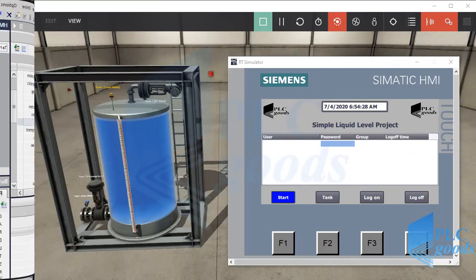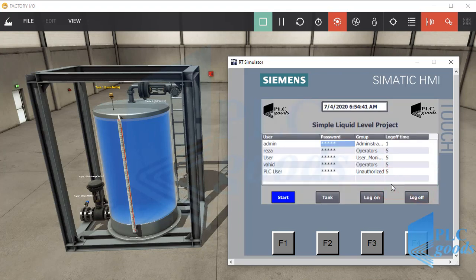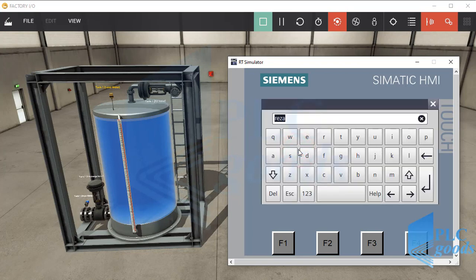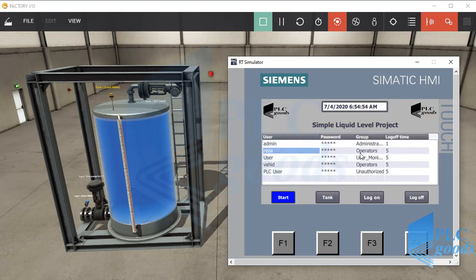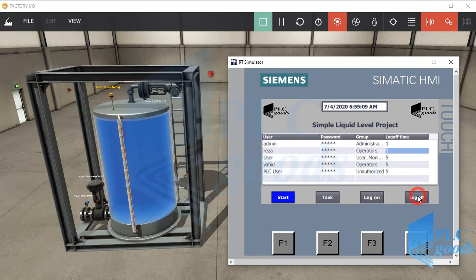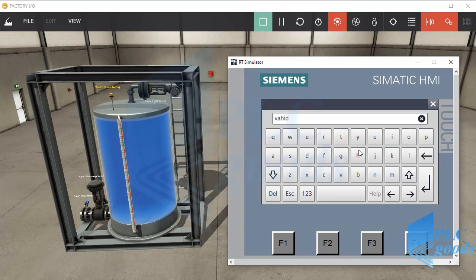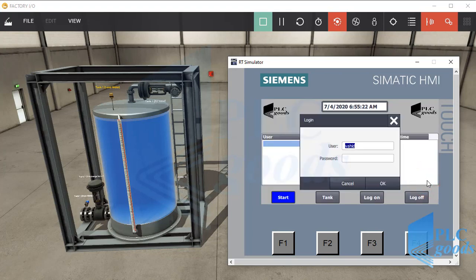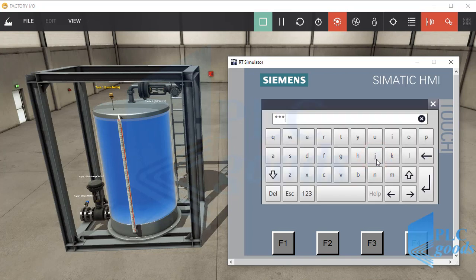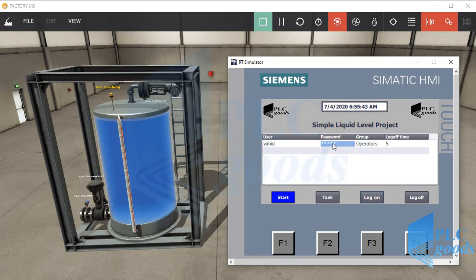Let's test the designed HMI. First, click on the user view table. Let me log on as admin, which has full accessibility. Now I can see all user information and change all usernames, passwords, user groups, and log-off time. Now let's log on with another user — this user can just change their password or log-off time.